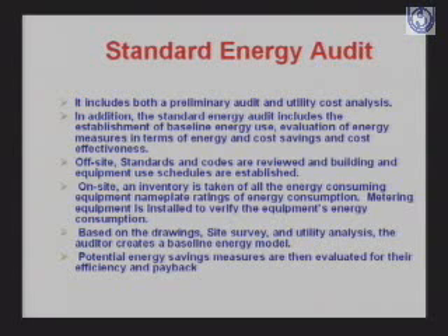Technically, one can estimate savings when switching from a CRGO transformer to an amorphous core transformer, based on losses and loading. This is technically correct, but management doesn't like to be convinced this way. They want you to project the baseline before retrofitting and the new conditions after implementation, so the before-and-after figures themselves speak of the impact of such retrofit measures.